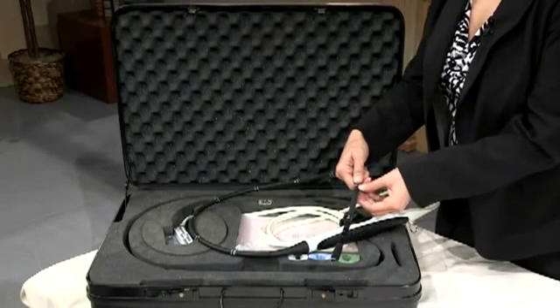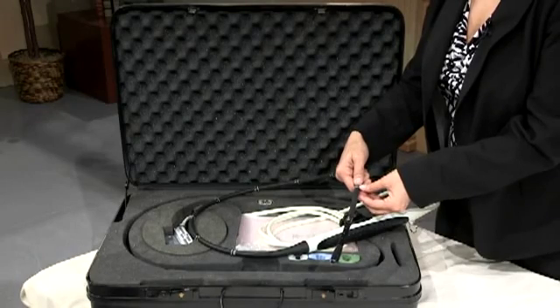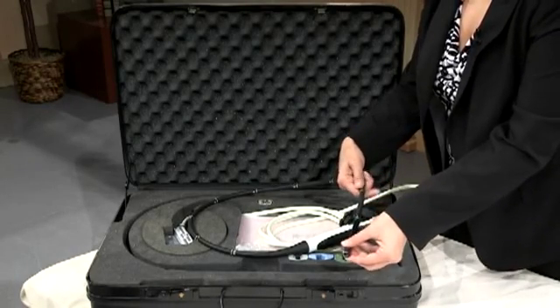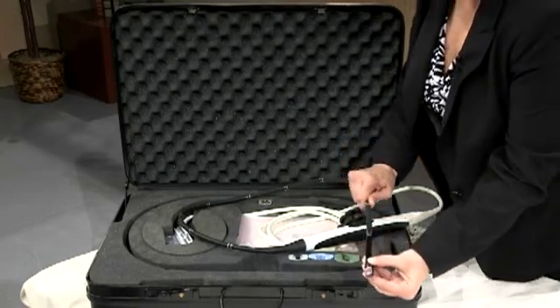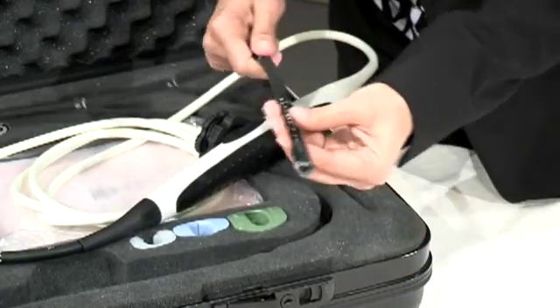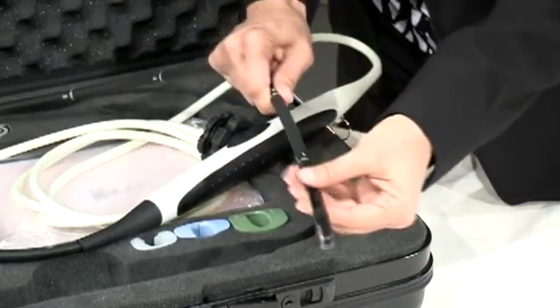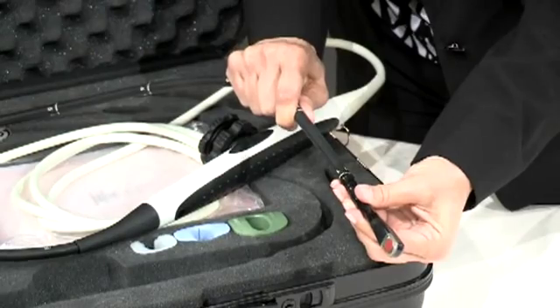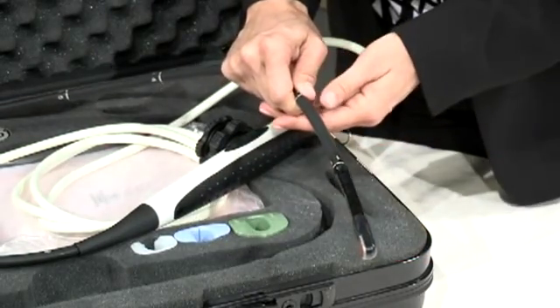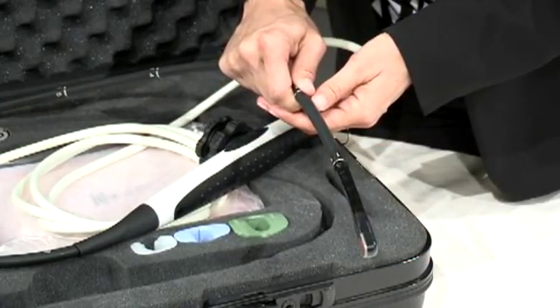It is recommended that you check the operation and physical integrity of the probe prior to patient scanning. If any irregularity is observed or suspected, the TEE probe should not be used. Please notify your service representative immediately of any damages or discrepancies.